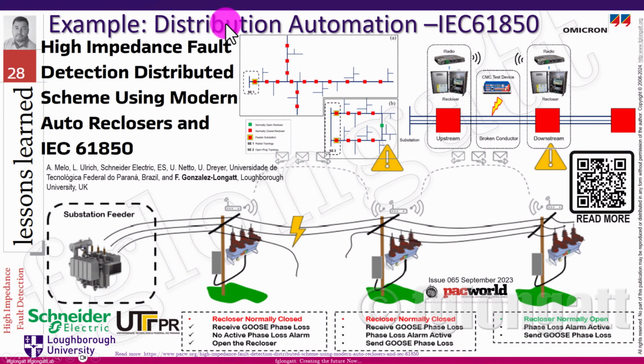All of you are related with the power utilities, and one of the most challenging situations is the detection of the high impedance fault. High impedance faults, as the name says, is a high impedance connected to one line or two lines to the ground, characterized by the fact that the current moving during the fault condition is relatively small and probably comparable with the load current.